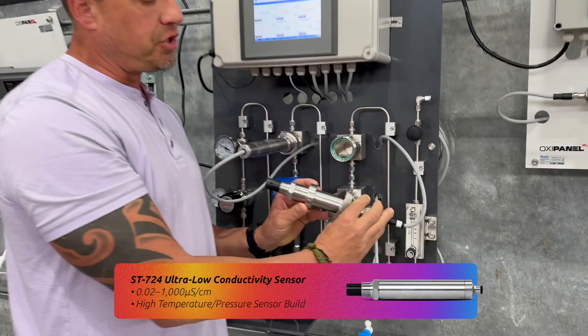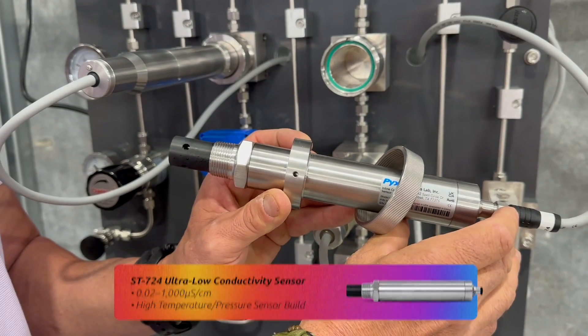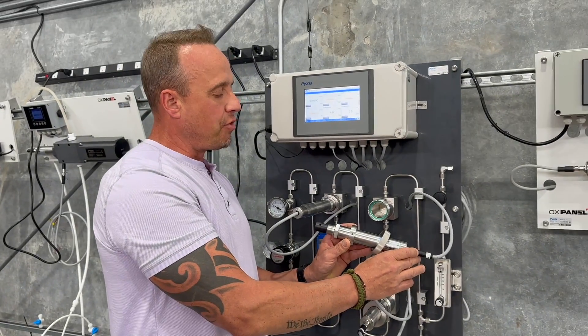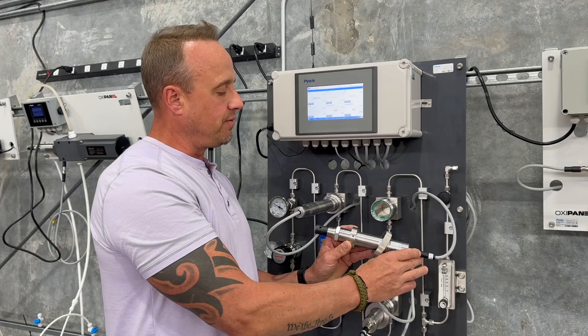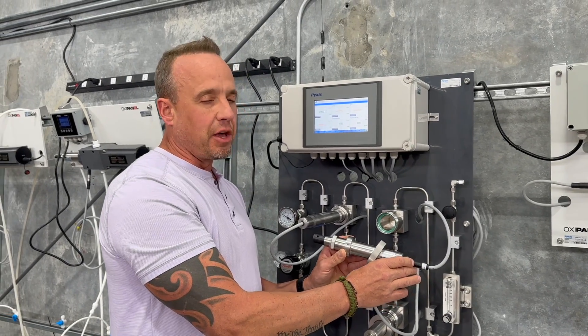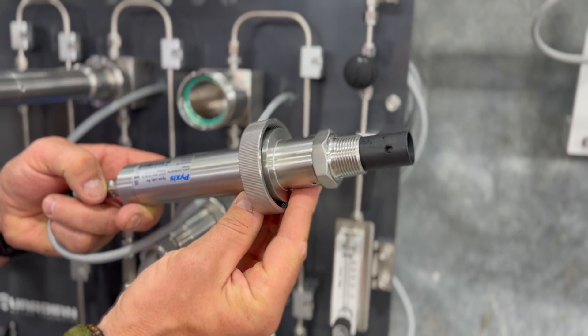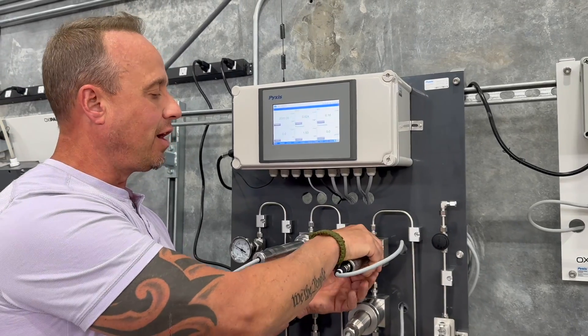The fourth sensor measures ultra-low conductivity in a range of 0.02 to 1,000 microsiemens — 0.02 equaling 50 megohm-cm resistivity. It's a broad range, ultra-low conductivity sensor, commonly used and valuable in boiler feedwater cycles of concentration monitoring in your boiler chemistry when compared to boiler water itself.